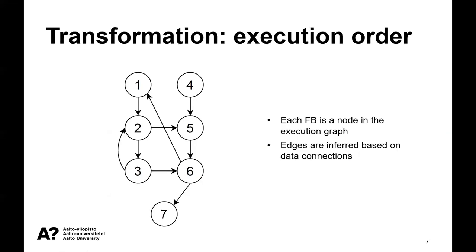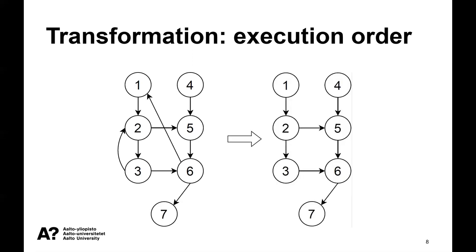But there are many systems that are already implemented in the IEC 61131 standard or just function block diagrams, and we need to transform them somehow to IEC 61499. How do we do this? We determine the topological ordering. We build this execution graph where nodes are function blocks and edges are inferred based on data connections.